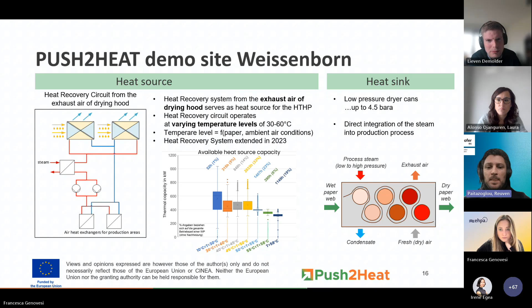The heat upgrade system at Felix Schoeller is a two-stage heat pump, extracting around 700 kilowatts of thermal energy at its design point, and upgrading this with two refrigerant circuits. The first is based on two screw compressors in parallel, and the higher stage works with two piston compressors in parallel, providing around 1.2 megawatts of steam at a pressure level of 2.3 bar absolute. The temperature lift in this system is around 80 Kelvin, which is quite high. Nonetheless, the design point for the COP of the system is at the level of 2.3.